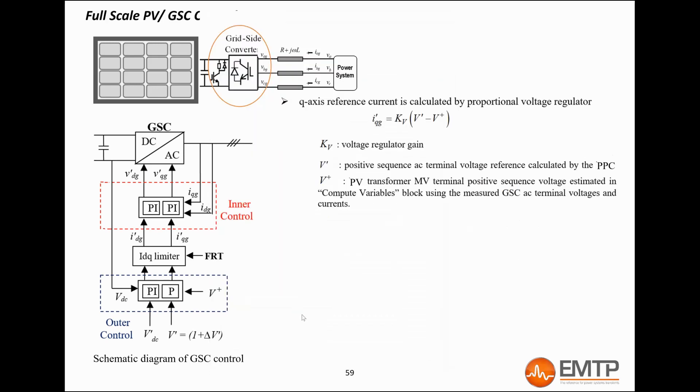The Q-axis loop now controls the Q-axis voltage in order to follow the voltage reference sent by the PPC for the park reactive power control. The outer loop produces a Q-axis current reference, which is also limited by the limiter and sent to the inner loop, which commands the Q voltage.